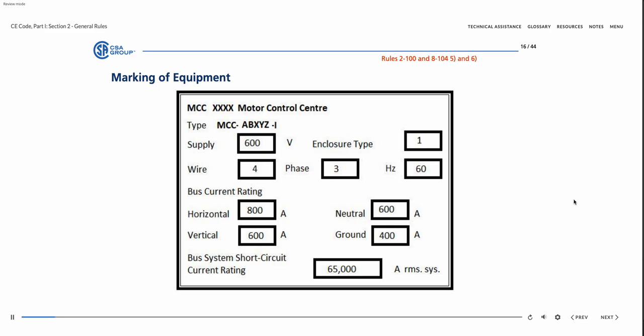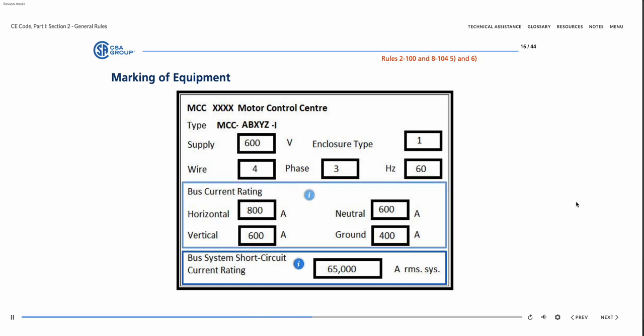New marking requirements include short-circuit current rating or withstand ratings and the maximum continuous load permitted for connection to a fused switch or circuit breaker. The marking for equipment requires the nameplate to have SCCR clearly visible. If the maximum continuous load permitted on a fused switch or circuit breaker, as determined in accordance with Rule 8-104, 5, and 6, is less than the continuous equipment load, the equipment shall be marked with the maximum permitted load.